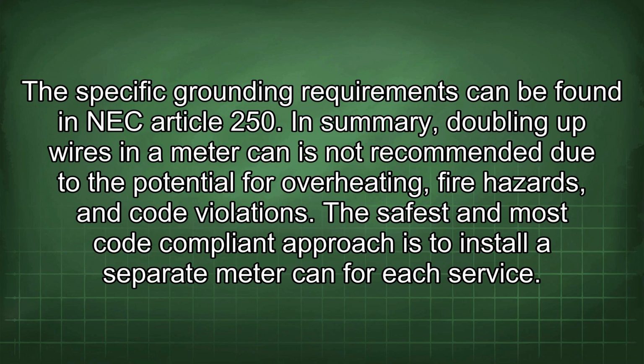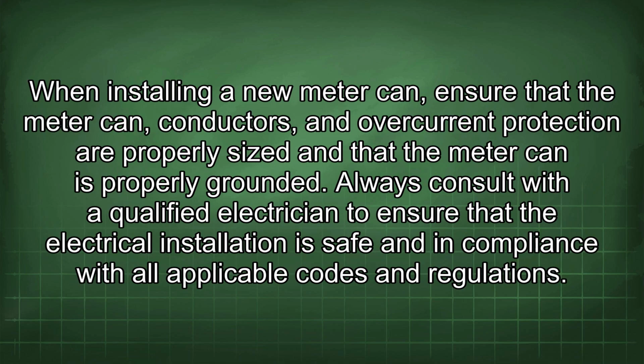doubling up wires in a meter can is not recommended due to the potential for overheating, fire hazards, and code violations. The safest and most code-compliant approach is to install a separate meter can for each service. When installing a new meter can, ensure that the meter can, conductors, and overcurrent protection are properly sized and that the meter can is properly grounded. Always consult with a qualified electrician to ensure that the electrical installation is safe and in compliance with all applicable codes and regulations.